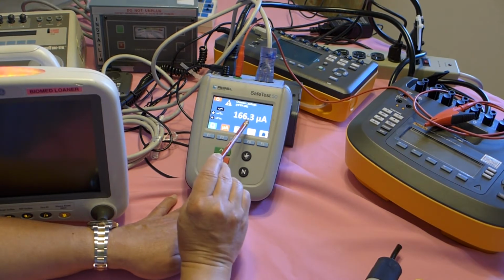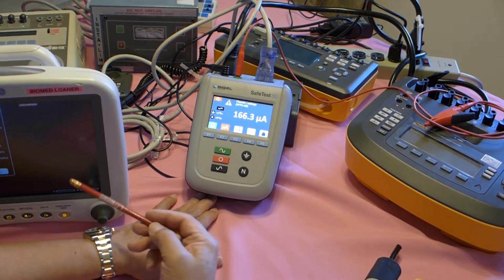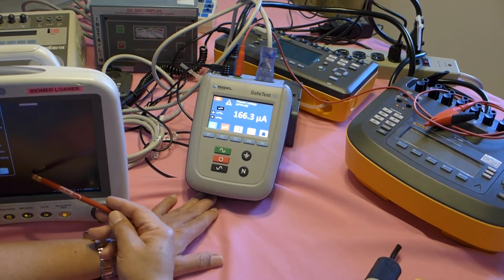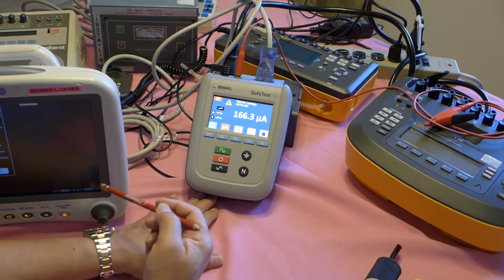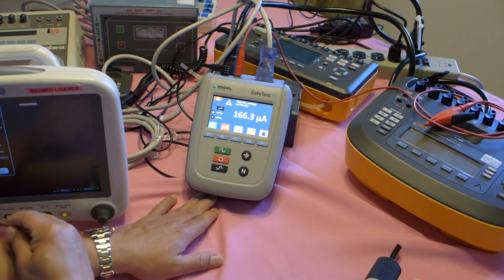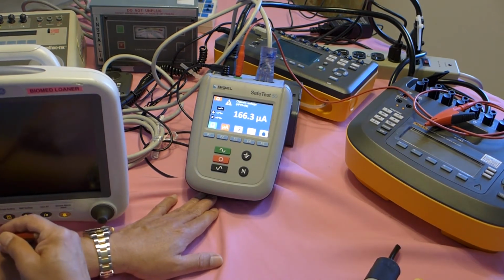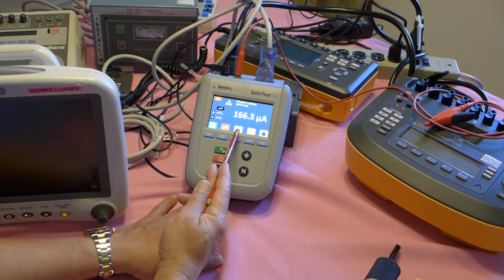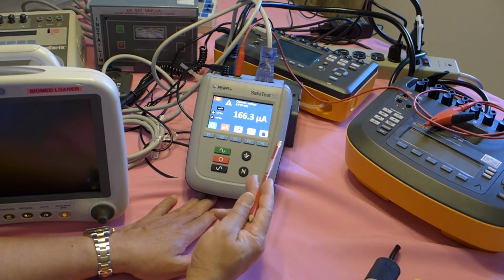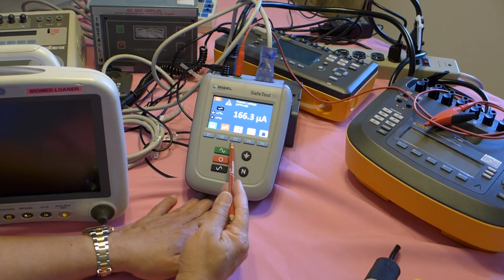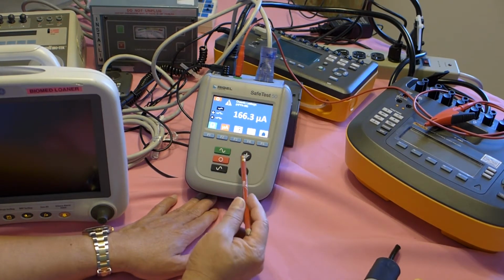So the maximum we're getting, okay, normally we see that the monitor will turn on. We can test that the monitor turns on, monitor turns off. Let's say you turn the monitor off, how much is it really? You still read at 166.3, which is fine, still below the safety limit of 500 microamps, which is the international standard now.